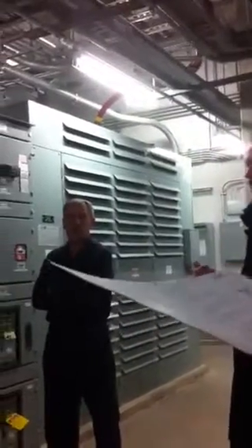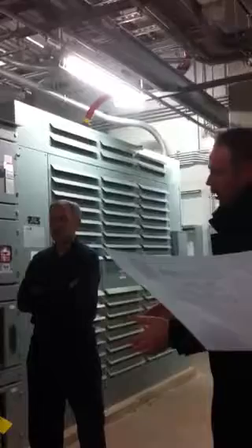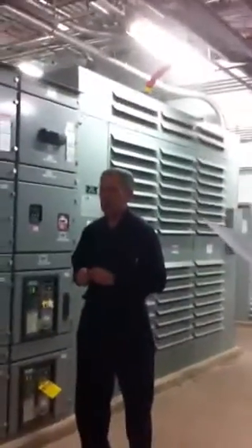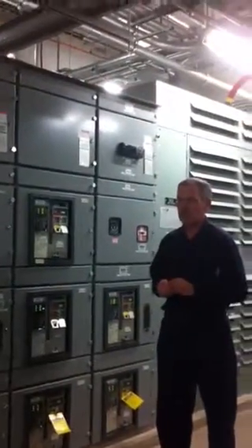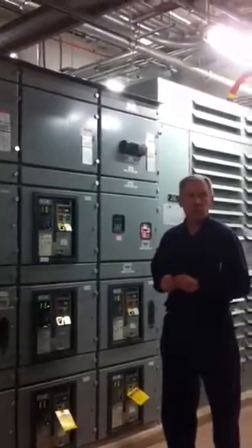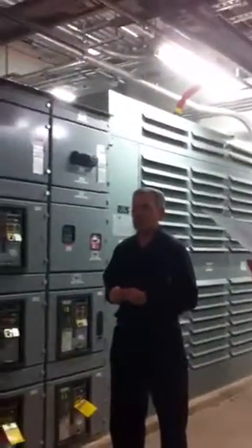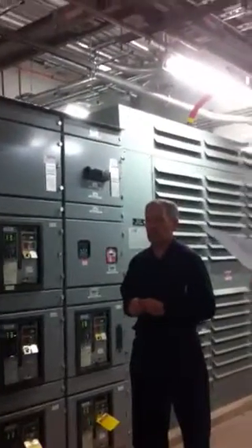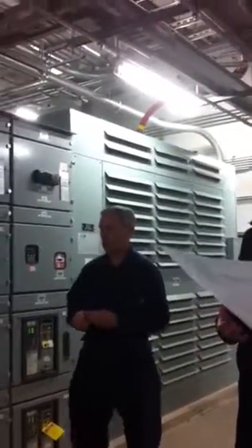So each of the boards, all of these breakers on here, you've got a main breaker for board number 1, a main breaker for board number 2. You have a tie breaker in the middle, and the rest of the breakers are sub-feeds. One feeds the east riser, one feeds the west riser, and then the other ones feed some other stuff. There's a normal power feed to the transfer switch, which goes all the way up to the roof, feeds the emergency distribution while normal power is in place, which is this guy, and then there's some other sub-feeds. There's a distribution board down here.